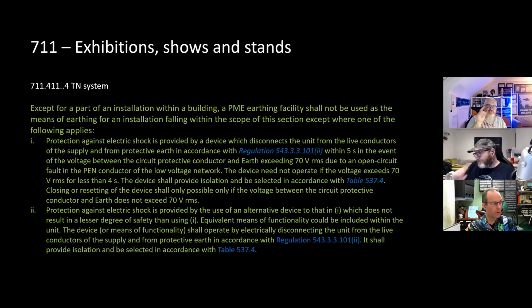I have said this to the chairman of JPEL, this needs to be in the main body of the wiring regulations. If we've had nearly 1,000 people injured a year from broken PENs, then we need to be installing this and taking measures. The trouble is the industry doesn't know what measures to take, because it would involve TTing potentially or isolating transformers and getting very, very complex.